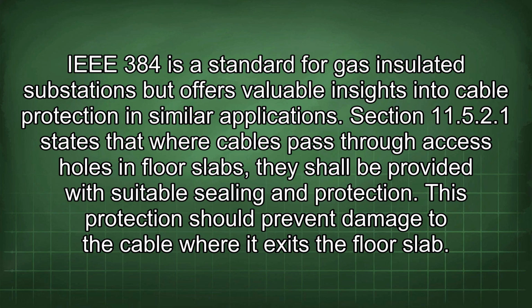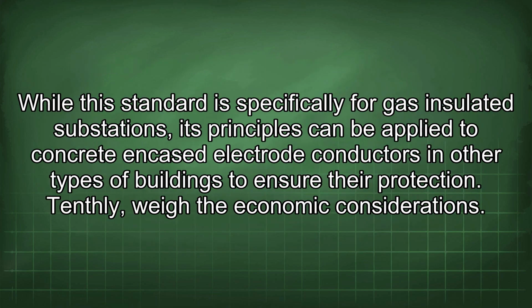Section 11.5.2.1 states that where cables pass through access holes in floor slabs, they shall be provided with suitable sealing and protection. This protection should prevent damage to the cable where it exits the floor slab. While this standard is specifically for gas-insulated substations, its principles can be applied to concrete encased electrode conductors in other types of buildings to ensure their protection.